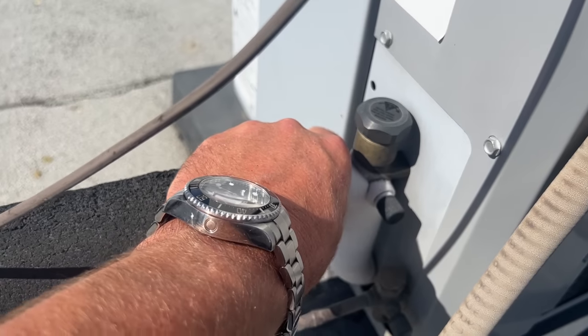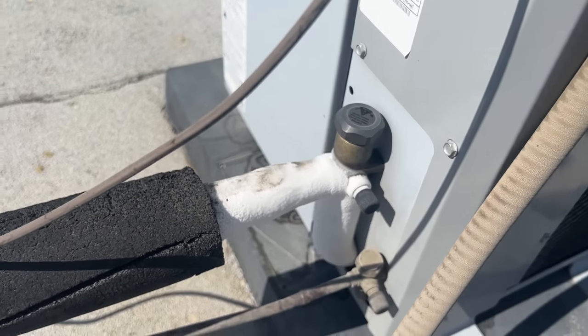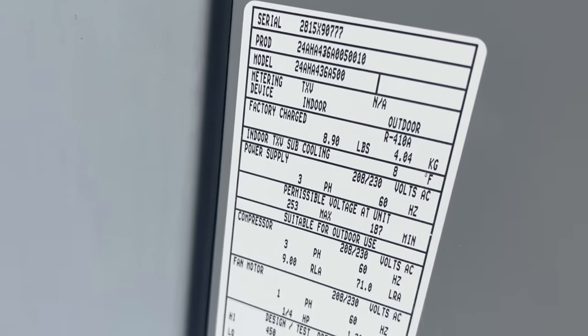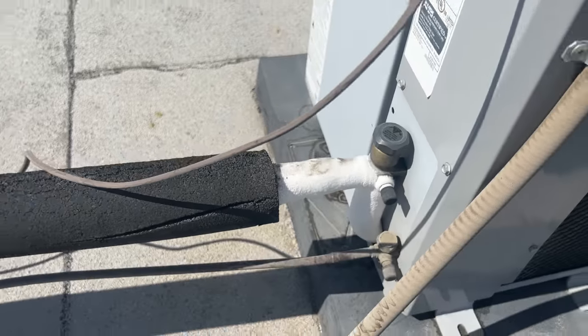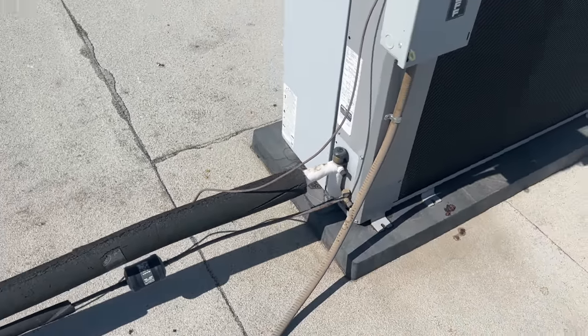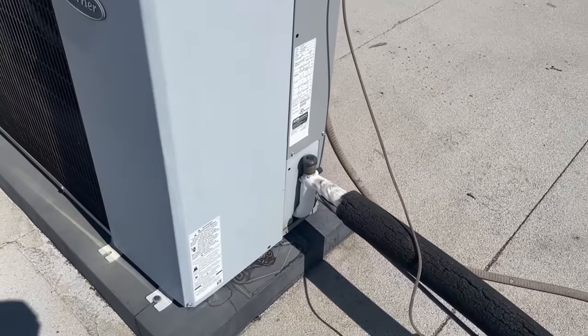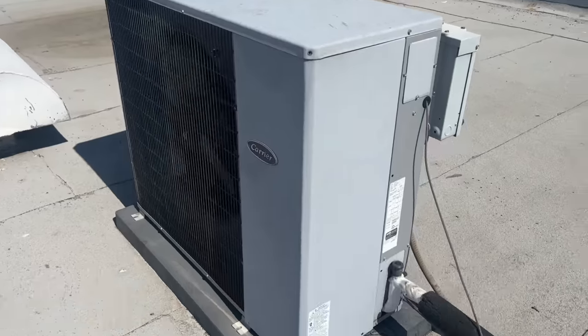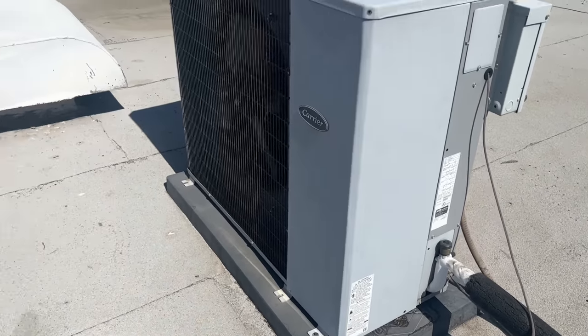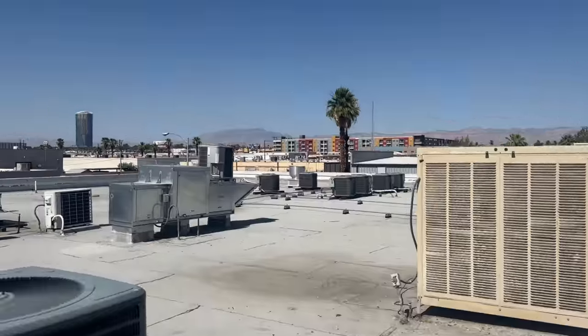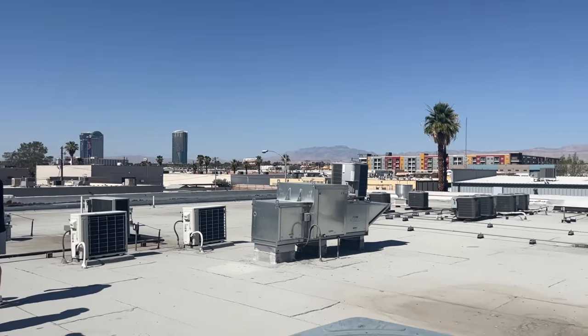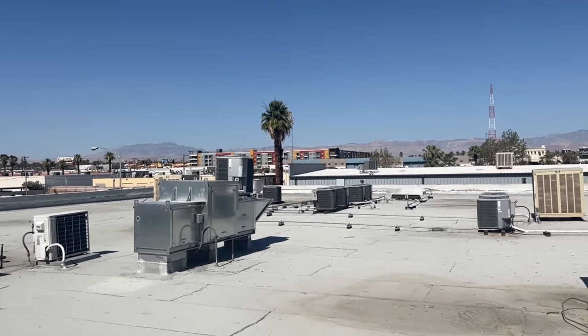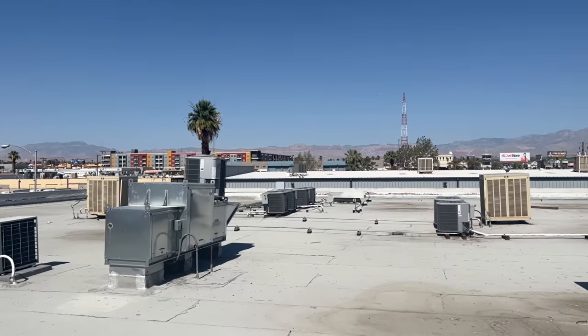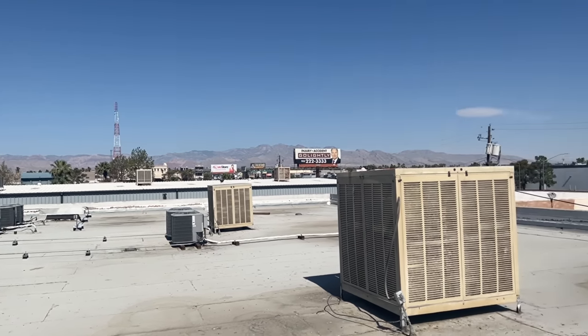So either we have an airflow issue, we could have a refrigerant charge issue, we could have a metering device issue, but it's not all 100%. We gotta find out why that's like that. I don't think it's gonna make or break the deal. We have an overkill amount of equipment here, overkill. But factoring in the BTUs of each metal halide ballast and bulb, that's the million dollar question.